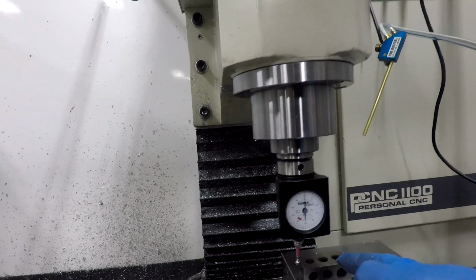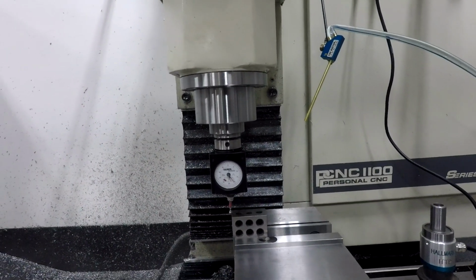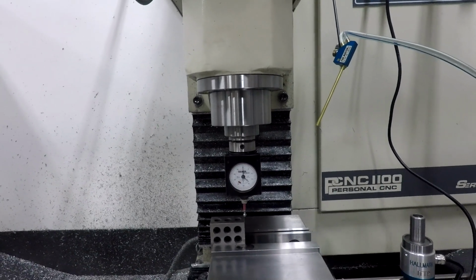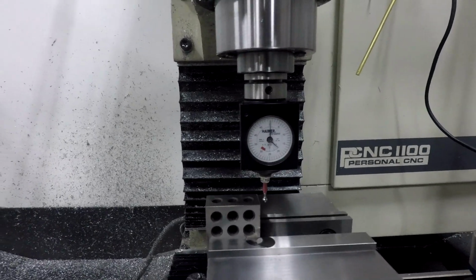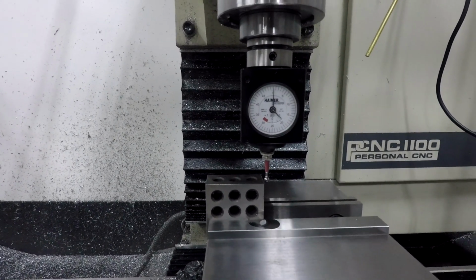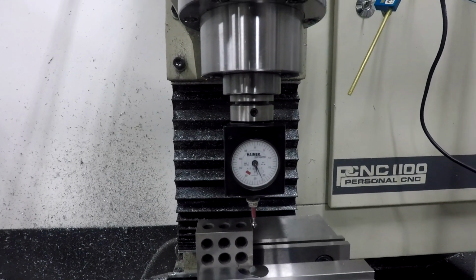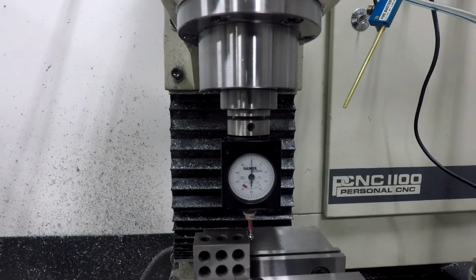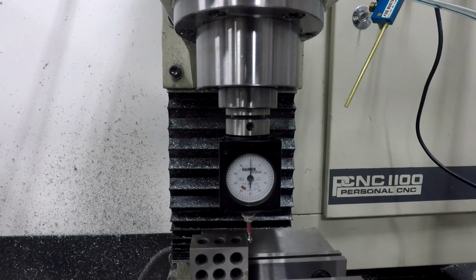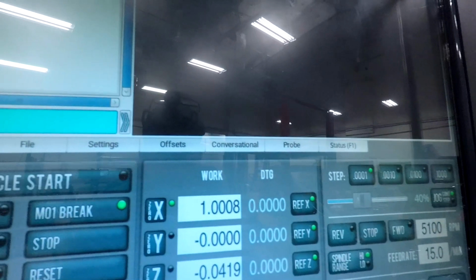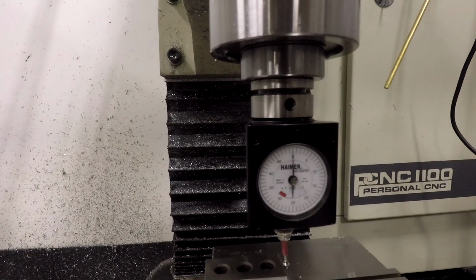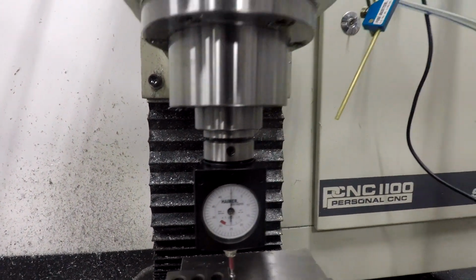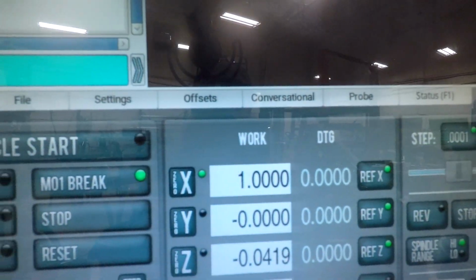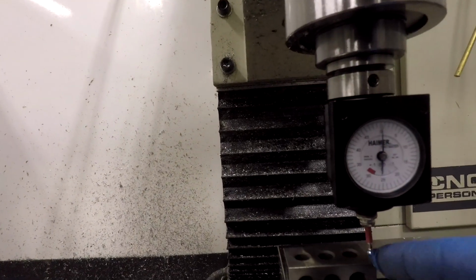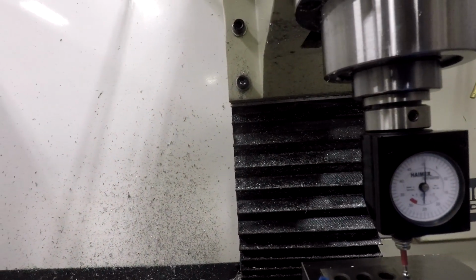So we're going to go to a +1 inch, and that's where we should be there. So I'm going to go ahead and go up. I'm going to go over this way. Go down. We should hit 1 inch. Backlash now, forward lash, and we are at 1.0008 inches. And if we took a little bit more out, the backlash that way, we're right on there. So we're actually right on when I did the backlash the opposite way because I'm on the other side. So that X is dead on 0.